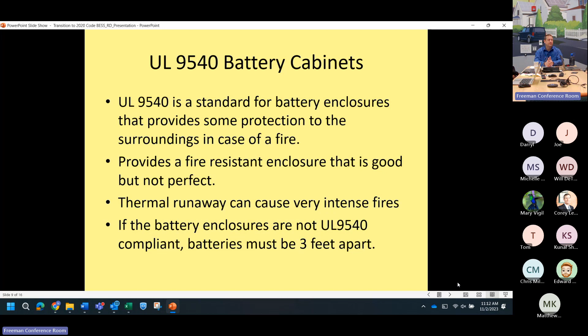Okay, so because the 9540 is not perfect, you have a sheetrock requirement. This comes out of the International Residential Code. You've got to use type X, which is fire rated sheetrock, and you have to protect the area around the battery. Now, what does that mean exactly, the area around the battery? In some cases, you may have to build a little 2x4 build out to sheetrock around the battery, and in some cases, just having the room, the basement area that it's in, sheetrocked is enough.